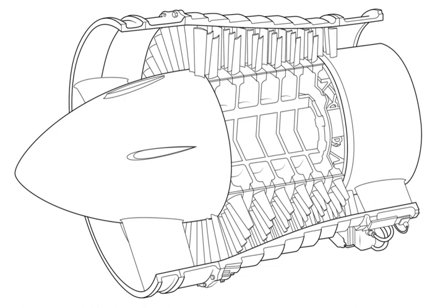The rotating airfoils, also known as blades or rotors, accelerate the fluid. The stationary airfoils, also known as stators or vanes, convert the increased rotational kinetic energy into static pressure through diffusion and redirect the flow direction of the fluid, preparing it for the rotor blades of the next stage. The cross-sectional area between rotor drum and casing is reduced in the flow direction to maintain an optimum Mach number using variable geometry as the fluid is compressed.